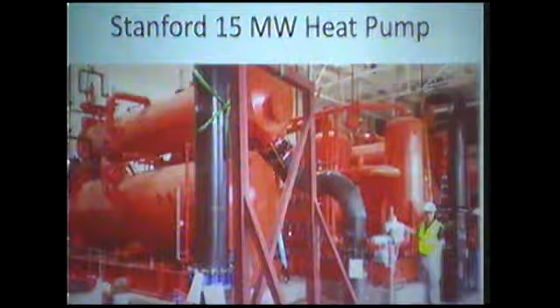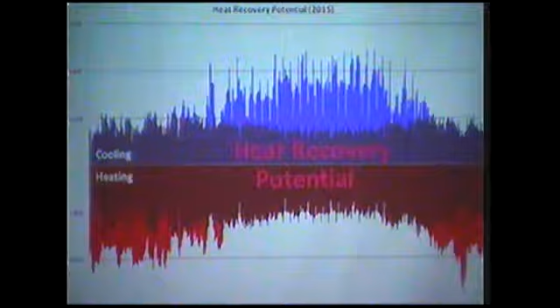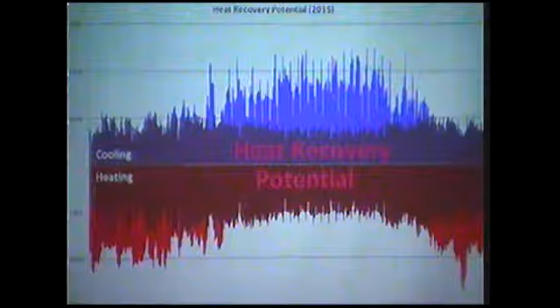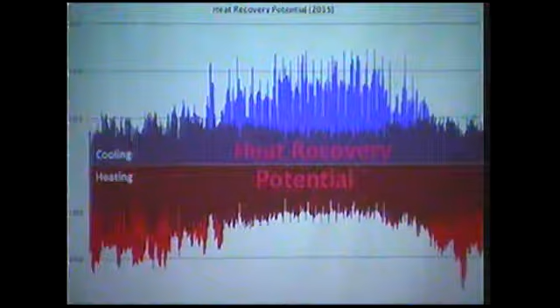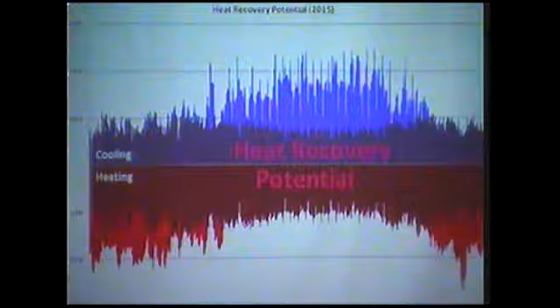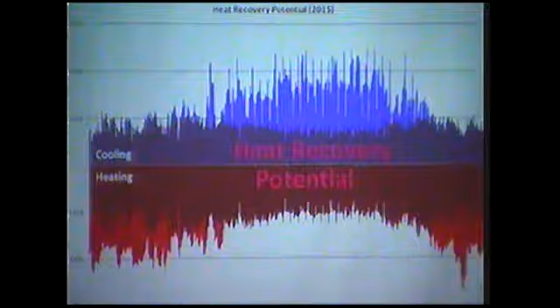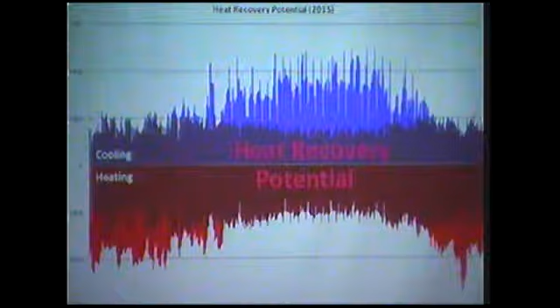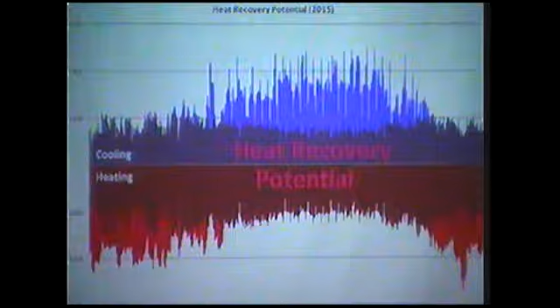All of that is being made surplus, and instead the campus is going to be cooled using heat pumps. To show you how that works, each building on campus actually receives both hot and cold water. The cooling and heating are roughly balanced with each other over the period of a year. That means the heat pumps will take the chilled water circulated to the buildings, which returns somewhat warmer, and the hot water circulated to the buildings, which returns cooler, and use heat pumps to transfer heat from the returned cooled water to the returned hot water — taking the energy out of what comes back and sending it out again.